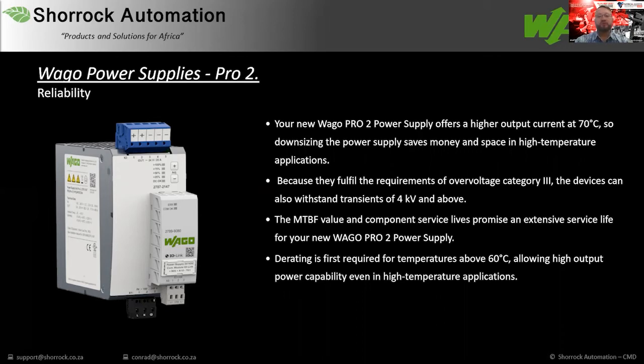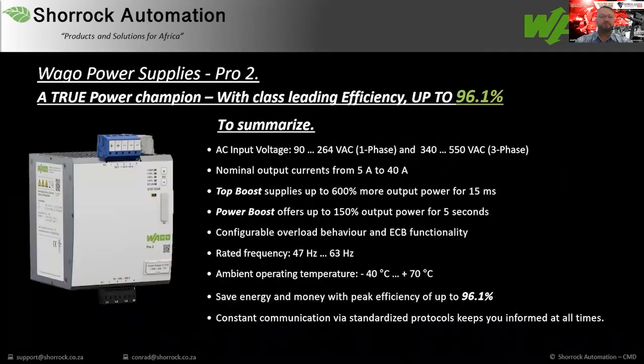Because they fulfill the requirements up to 4 kilovolts and above. The mean time between failure value and the component service life promise an extensive service life for your new WAGO Pro 2 power supply. Derating is first required for temperatures above 60 degrees Celsius, nothing before that, allowing for high output power capabilities even in high temperature applications.